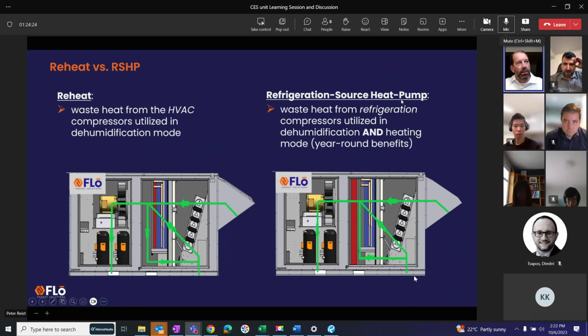And a refrigeration source heat pump does not care about the entering air temperature. In fact, the colder the air that hits that coil, the more heat it gives us, because we want a high delta T. So it's kind of opposite from all the other heat pump rules that you may know in your mind. We love outside air on this type of technology.